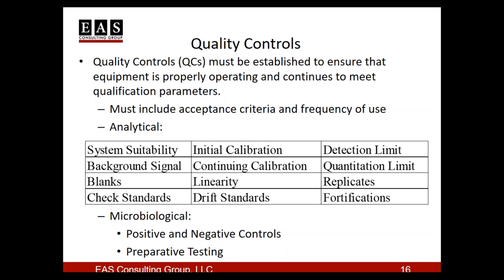For analytical instrumentation, there are a lot of different QCs that can be utilized—I've just listed a few here. System suitability, which is an injection of a standard five times to make sure we have the appropriate precision of the instrument before we start to analyze our samples. The incorporation of blanks and check standards to make sure our standard is recovering appropriately. Drift standards is another one—every so many injections, maybe 10 or 15, on a chromatographic piece of equipment, we re-inject a standard and verify everything is still within control. With the automation afforded now with equipment, there are auto samplers that have 500 locations and they're refrigerated.